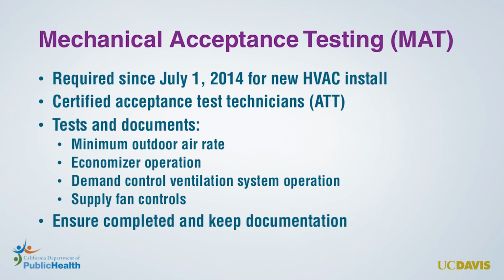Effective July 1, 2014, California mandated that all new HVAC systems in commercial buildings undergo mechanical acceptance testing to verify the proper functioning of the system upon installation. Effective October 1, 2021, California introduced an additional requirement that only certified acceptance test technicians, or ATTs, can conduct this assessment. It's critical to ensure that this testing is performed when installing new HVAC systems and to maintain these records.